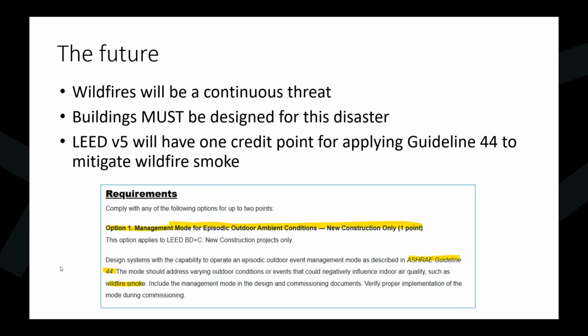At this time, the guide you've seen here is still not code, but it's a good best practice. Even in LEED version 5, which will be deployed soon, there's a strong emphasis on the building being resilient, and one of those resiliency measures is managing wildfire smoke. If you apply guideline 44 and have a smoke readiness plan, LEED version 5 will now give you 1 point for that.